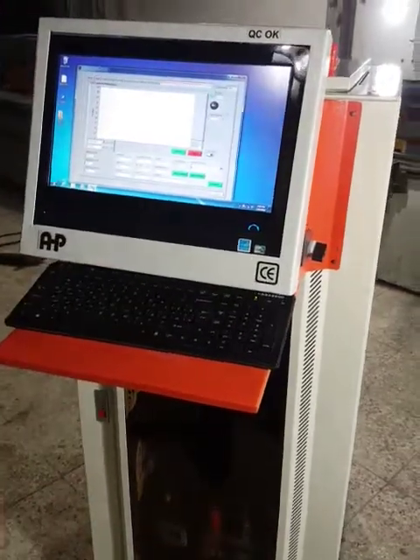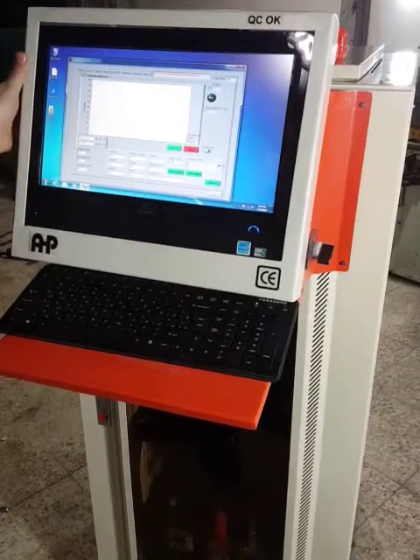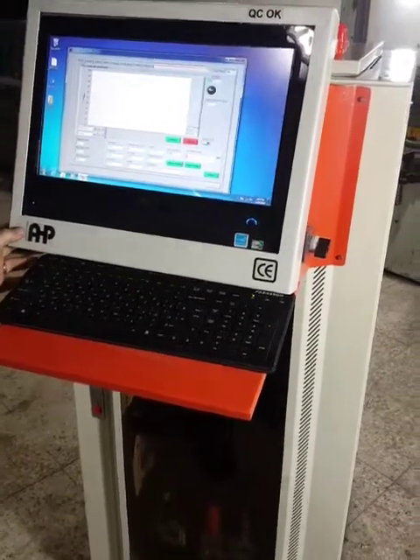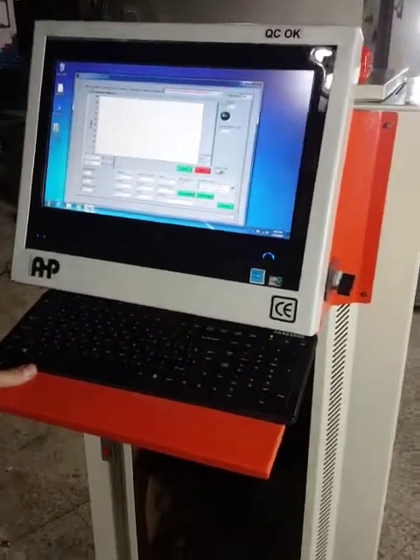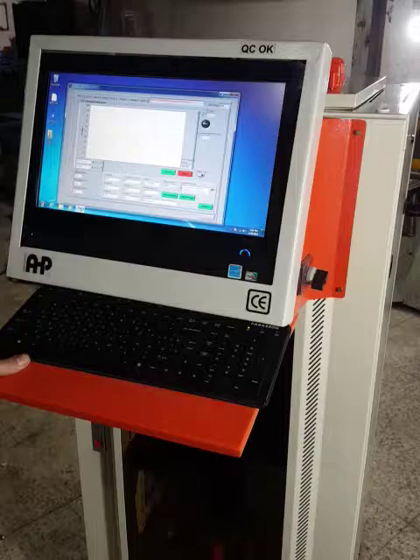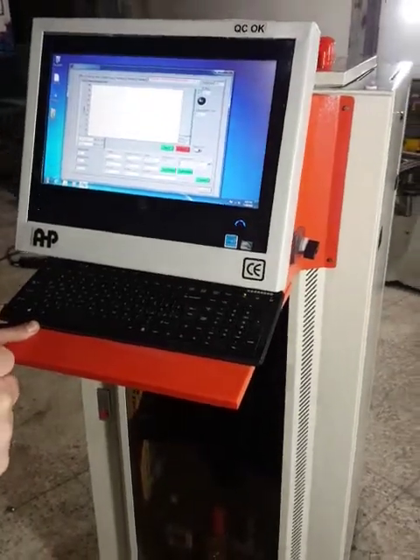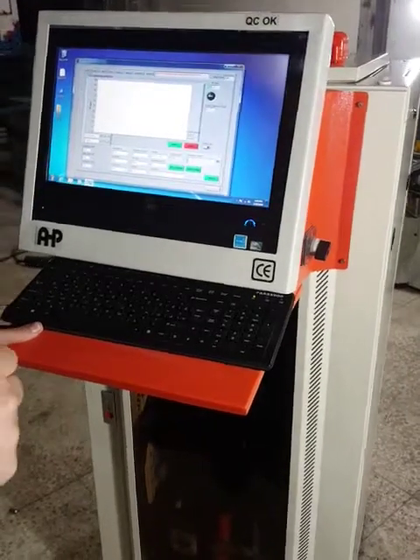In this video I'm going to present our hydrostatic testing unit. This is the AHP four-channel hydro unit. The machine is capable of supplying four separate pressure channels up to 100 bars.